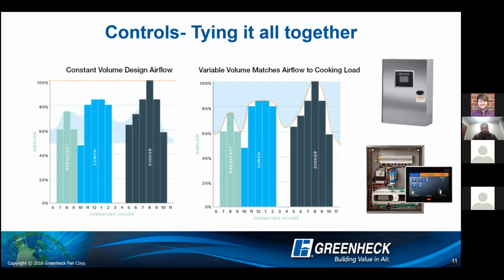Now, when do you use a variable volume system? So IECC 2015 states that anytime you have over 5,000 CFM in the exhaust system, you need to have a variable volume system, and it is recommended that that system be able to turn down 50%. Now, Greenheck has the product offering on our variable volume systems, when you have a direct fired makeup air fan, the Greenheck variable volume system has an industry-leading 50% turn down based on the capabilities of our direct fired units.